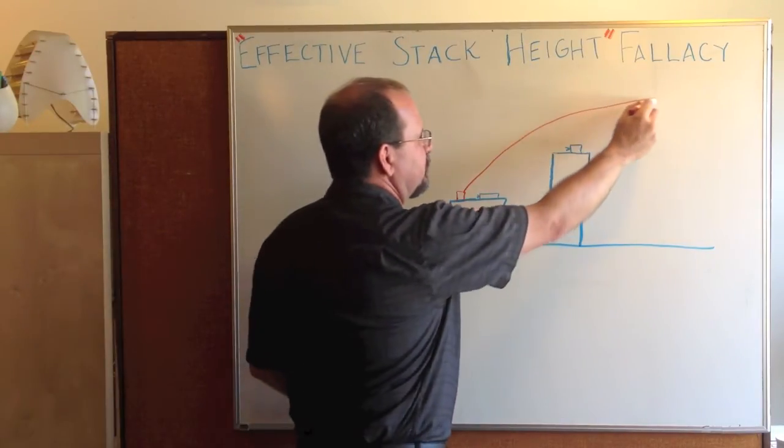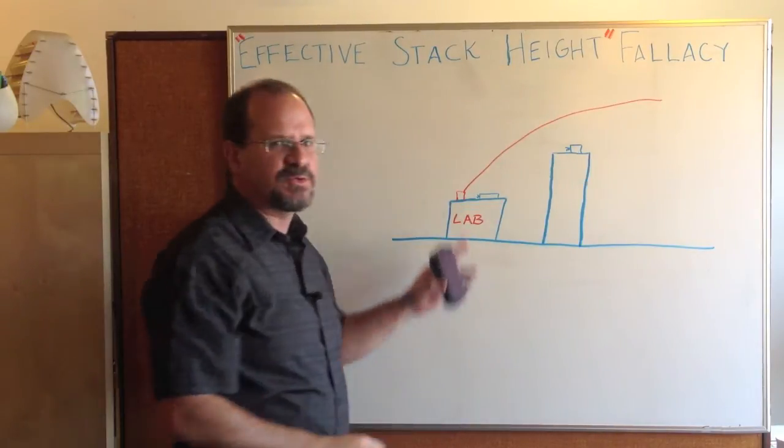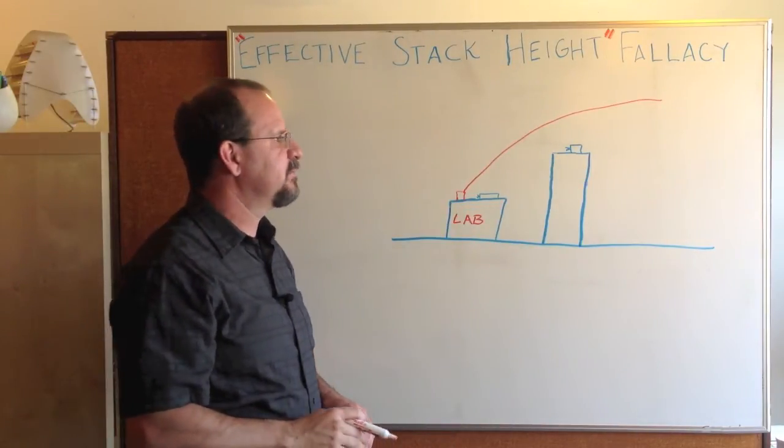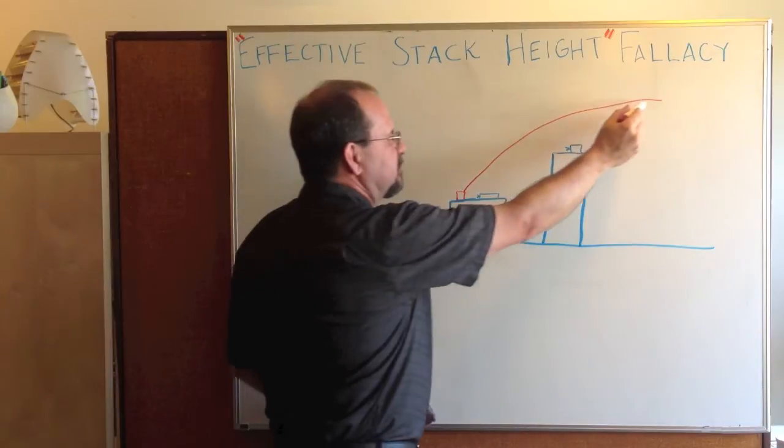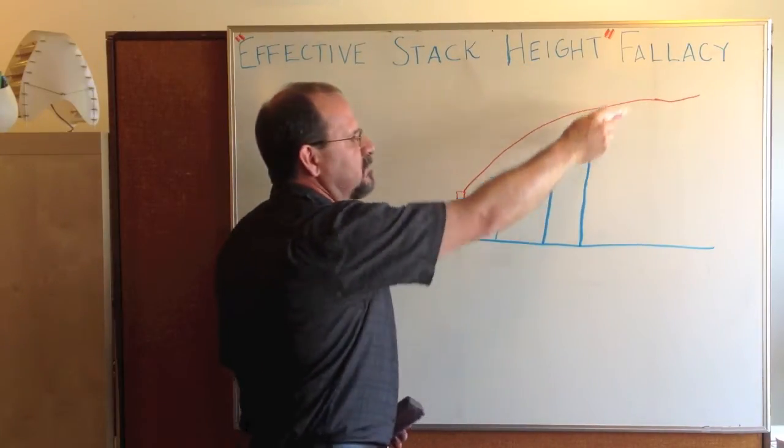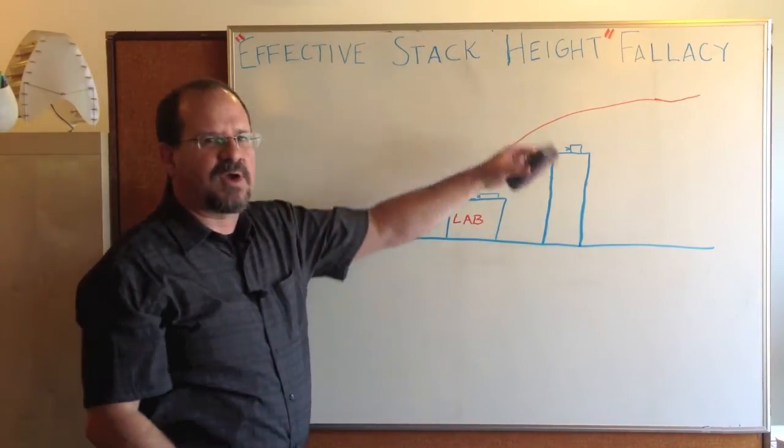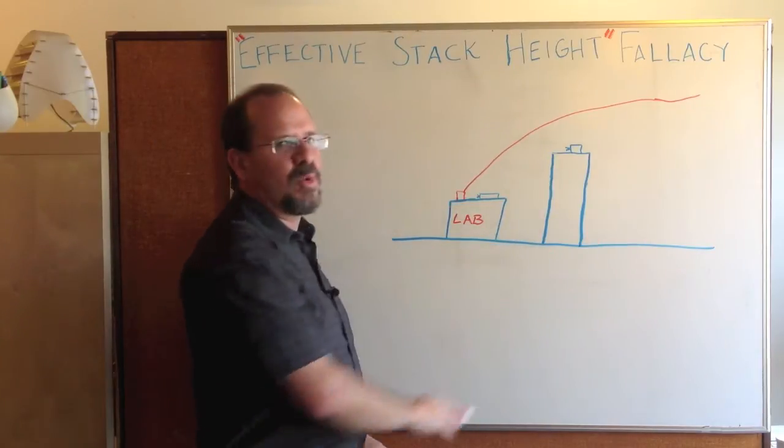In the ASHRAE handbook, there's a series of equations that you use when you're doing laboratory exhaust design that predict plume rise. They predict it all the way out to some highest point, some final rise that happens a long way downwind.